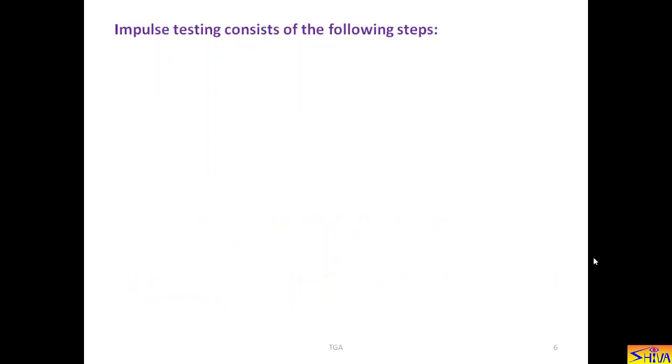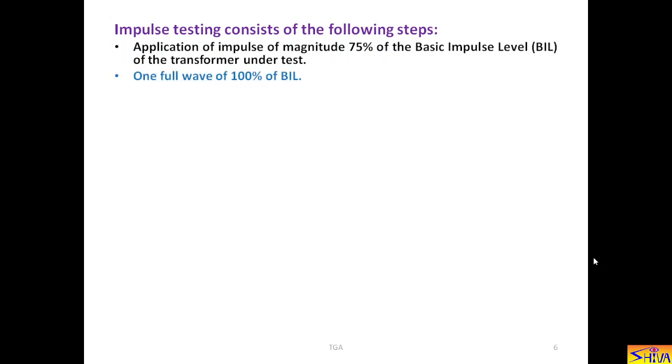Now, let us see what are the steps involved in impulse testing of the transformer. First, application of impulse of magnitude 75% of the basic impulse level of the transformer under test is applied. So, if BIL of the transformer is 1000 kV, then impulse voltage magnitude peak value should be 750 kV. And it is applied to the transformer under test.